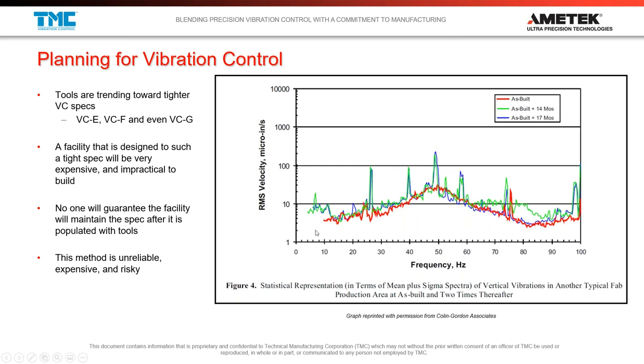So you kind of see this resonant frequency of the facility. Well, 16 or 17 months and 14 months later, they went back in after the fab was completely populated, and we saw increases, especially at low frequencies, of 10 times what was there initially. So this is very, very common. You're always seeing more and more vibration in the facilities.